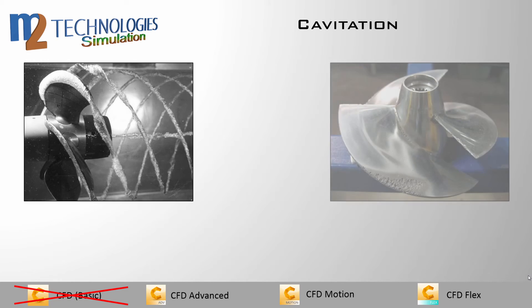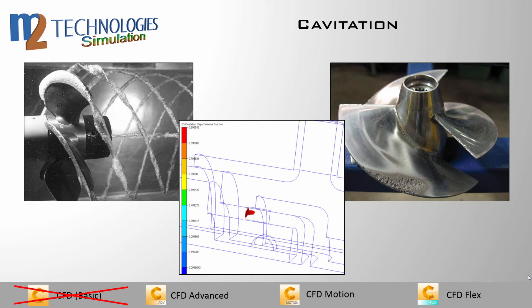Cavitation is a physical phenomenon that occurs in many high-velocity liquid flows. When the liquid pressure falls below the vapor pressure, vapor bubbles form in the liquid. Cavitation is commonly found in high-performance valves, flow control devices, pumps, and propellers, and can greatly reduce the efficiency of these devices. Prolonged cavitation leads to pitting and erosion of the device, resulting in costly downtime and repairs. The cavitation model tracks the vapor bubble volume fraction and predicts the onset and location of bubble formation within the flow.